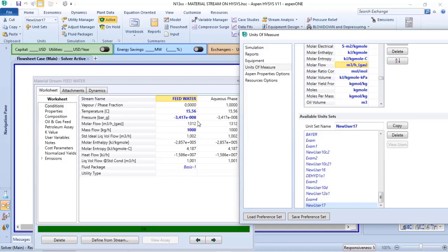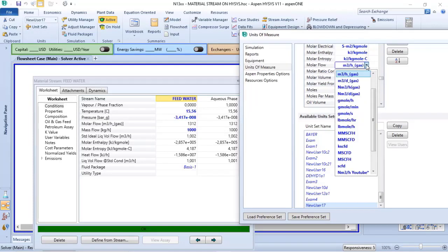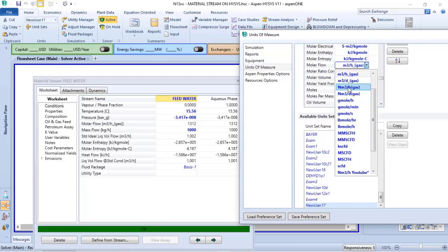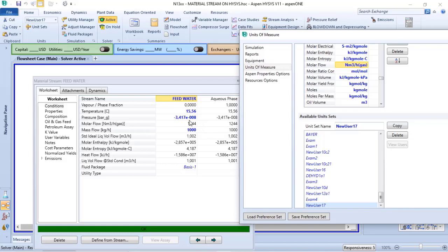Now what I have here is the conversion of 1,000 kilograms per hour of water to a gas flow. If I change to normal cubic meter per hour of gas, my value will change from 1,312 to 1,244 normal cubic meters per hour of gas.